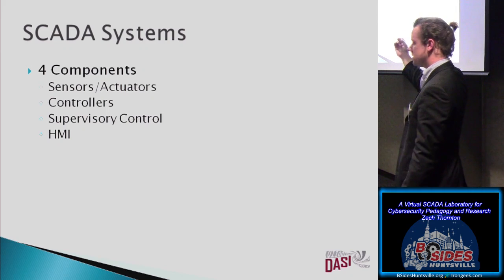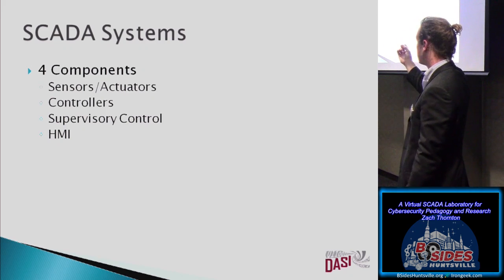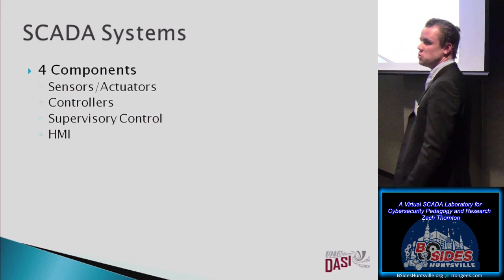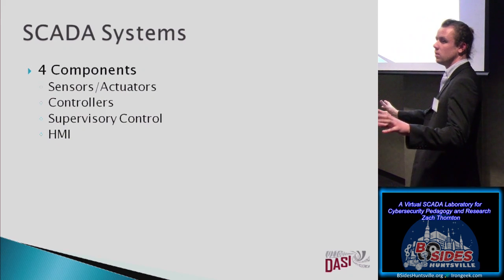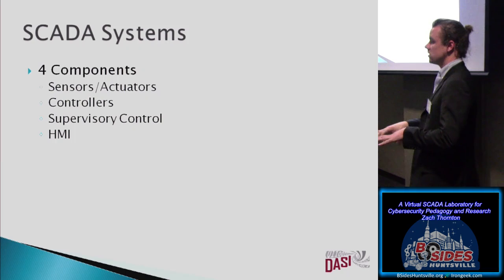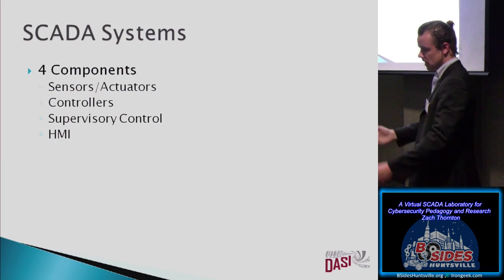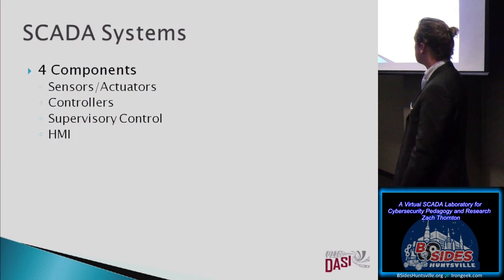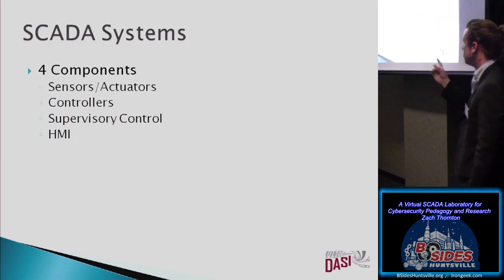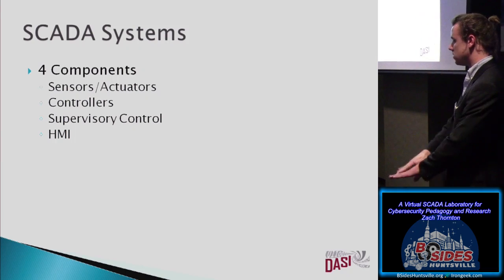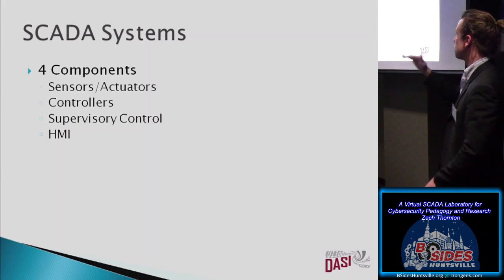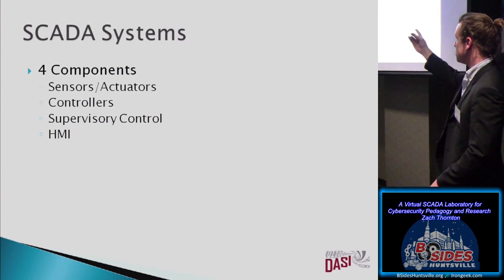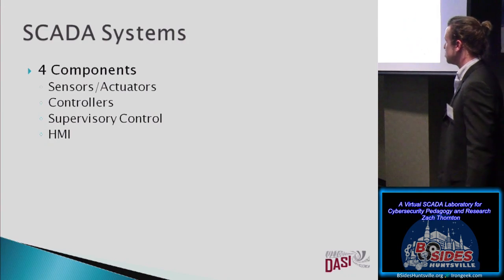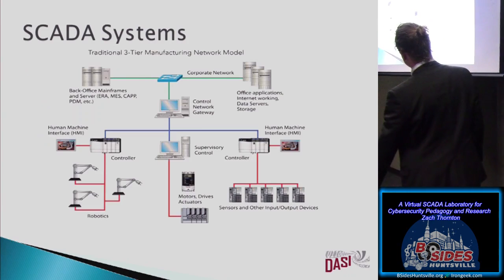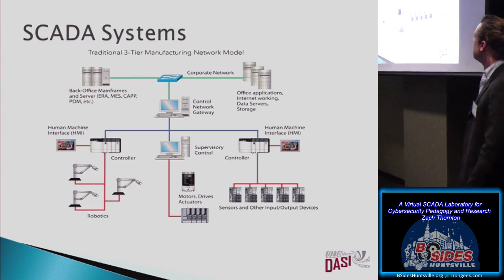HMI is basically the same thing as a GUI in modern times. It's a display so you can see the whole process going on, like when an operator is sitting in a control room looking at a display. Supervisory control usually sits above that - so if you have sensors reporting to controllers, and you can see it on an HMI, the controllers will go up to supervisory control. That's kind of confusing, so here you go.